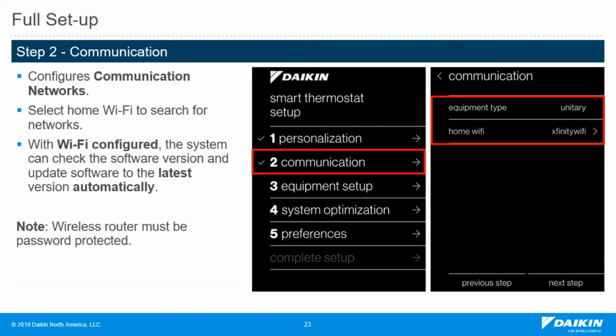The communication tab is an important tab. That's where we'll set up the Wi-Fi. It's important to set up the Wi-Fi as quickly as possible. Maybe very first thing when it comes on, it will reach out to Daikin and do a system update right away. Within the first 20 minutes of being booted up and the Wi-Fi operational, it'll reach out to Daikin and you'll have the newest version. If you're going to be in an area where you do not have Wi-Fi, you can hotspot to your phone as well. Very small data packet to update it. When you do make a connection, keep in mind you must be password protected.